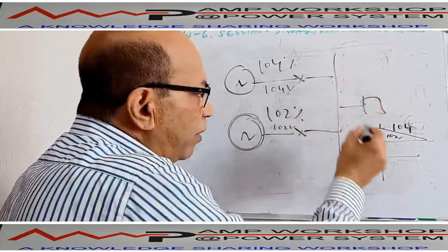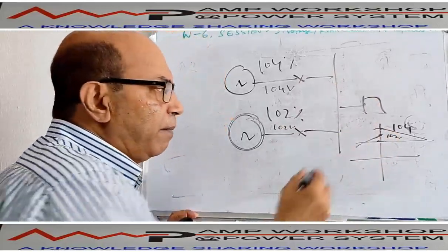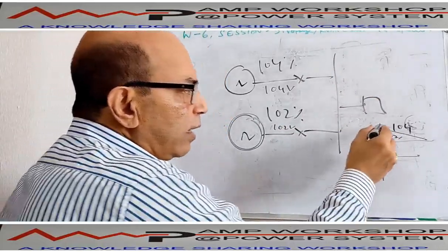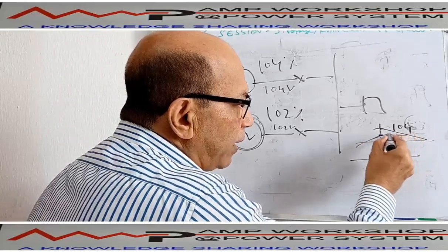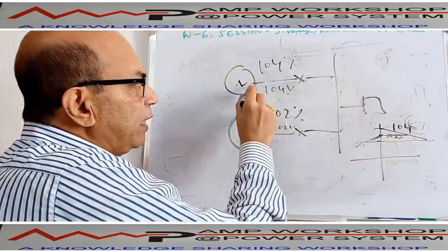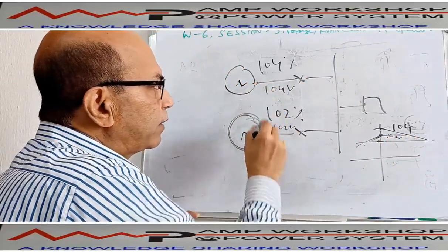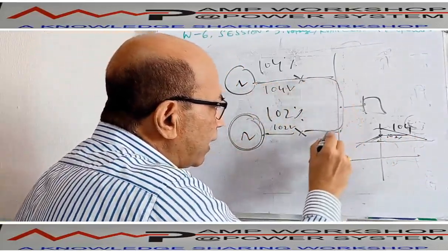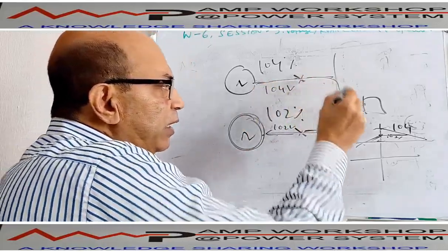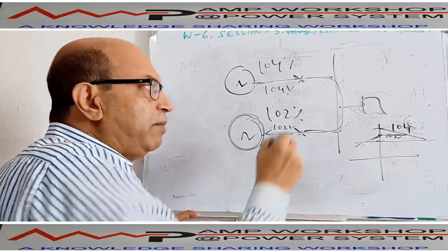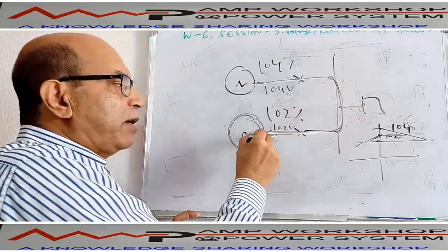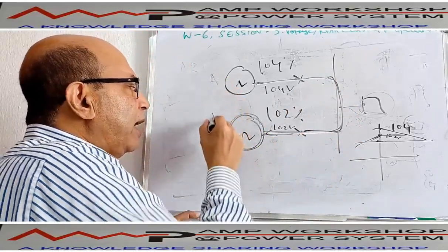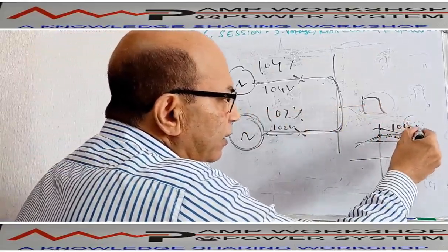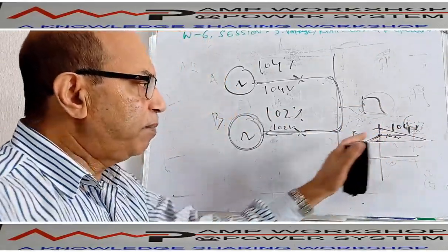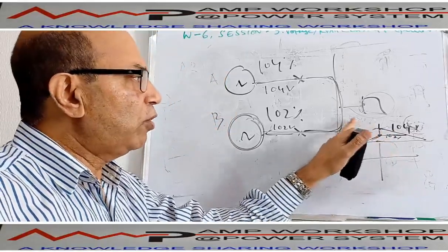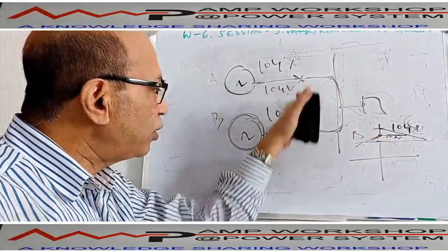The moment load comes over here, this machine will take the load. But what will this other machine do? Until the load voltage comes over here, this machine cannot feed power, because here the voltage is more, here the voltage is less. So actually it will draw the current this way. It will cater the power to the load, and at the same time it will cater some reactive power to the other machine. Suppose this is A machine and this is B machine. This is A machine characteristics, this is B machine characteristics. As the B machine has a lower voltage, reactive power will flow from A machine to B machine.